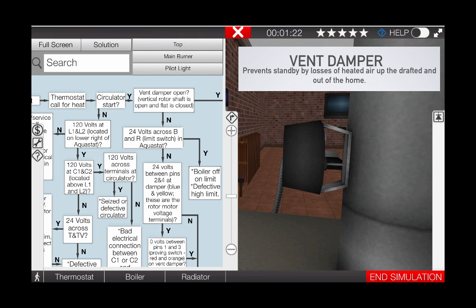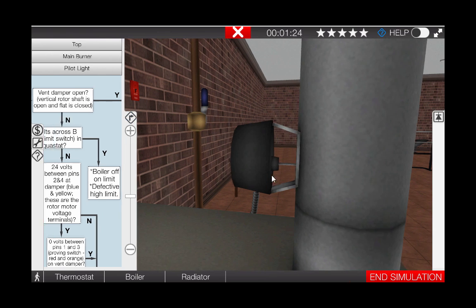The vent damper includes both the motor to drive the damper as well as a proving switch that verifies that the damper did in fact open prior to allowing burner ignition.